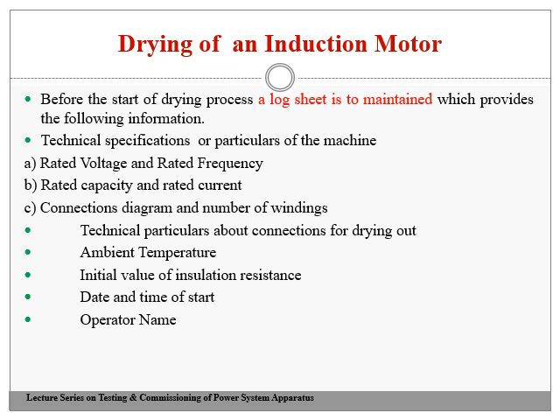Therefore, before the start of a drying process, a log sheet is maintained, which provides the following information. The log sheet should have the technical specifications or particulars of the machine under the drying process, like rated voltage, rated frequency, rated capacity and rated current. Then the connection diagrams and the number of windings.